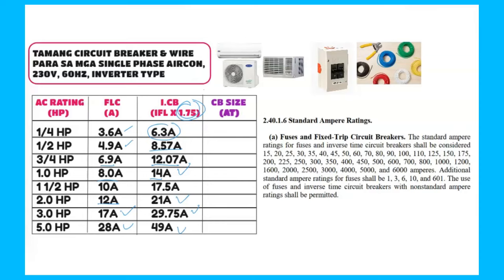So merong standard ang Philippine Electrical Code from 2.40.1.6, standard ampere ratings, that is for fuses and fixed-trip circuit breakers. So the standard ratings for fuses and inverse time circuit breakers shall be considered as 15, 20, 25, 30, 35, 40, 45, 50, 60, and so on. And but may sinabi yung code na dapat daw yung circuit breaker ay hindi siya bababa ng 15 amperes.